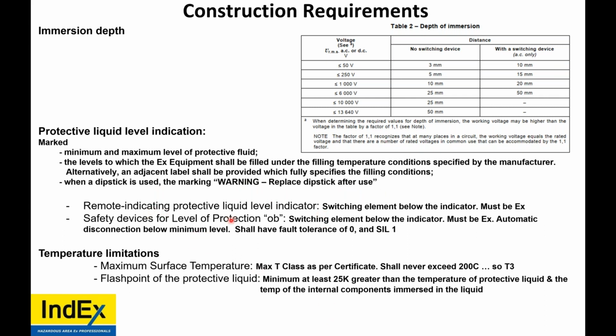Now, remote indication, the switching element needs to be below the indicator, and it must be EX. It must be rated for hazardous areas. Now, safety devices for Ex ob, the switching element must be below the indicator, it must be EX, but also it has to have automatic disconnection of power below the minimum level. And it shall have a fault tolerance of 0 and a SIL level of 1, okay? Safety integrity level.